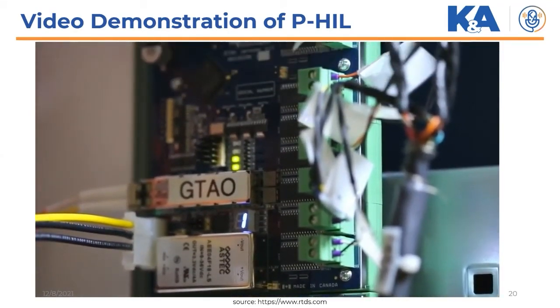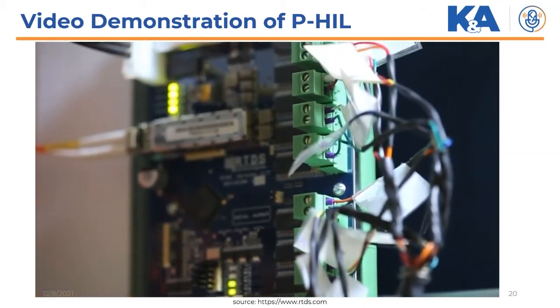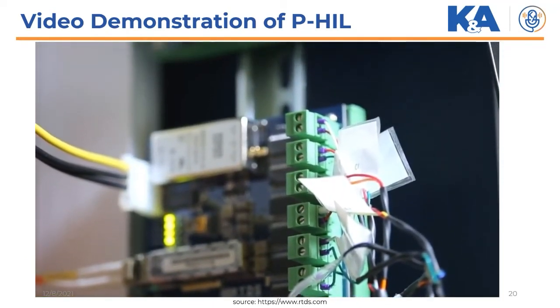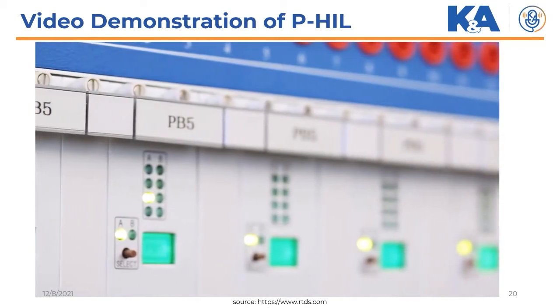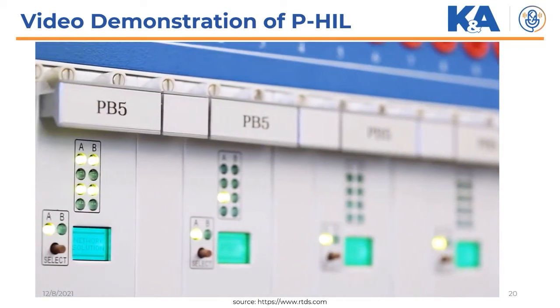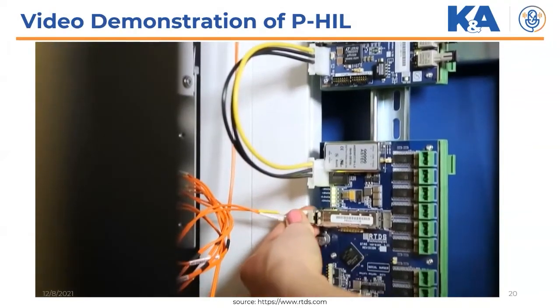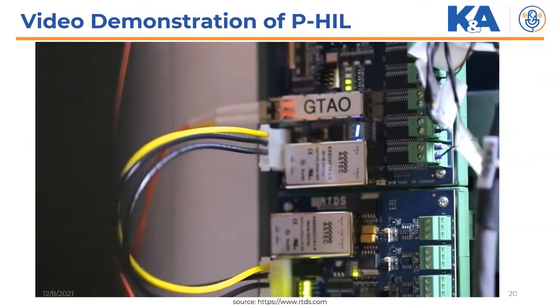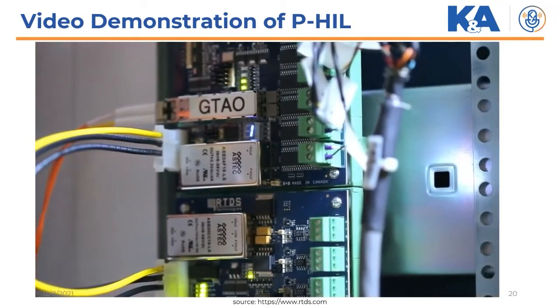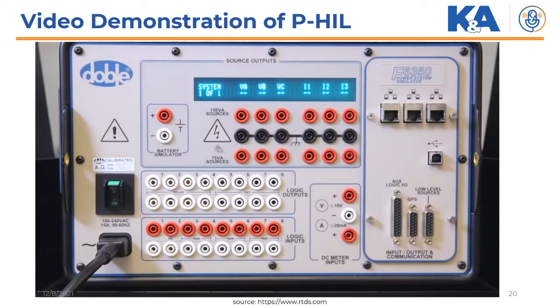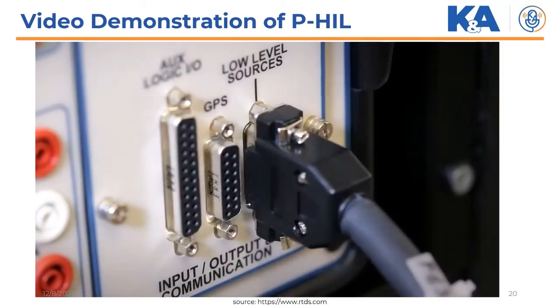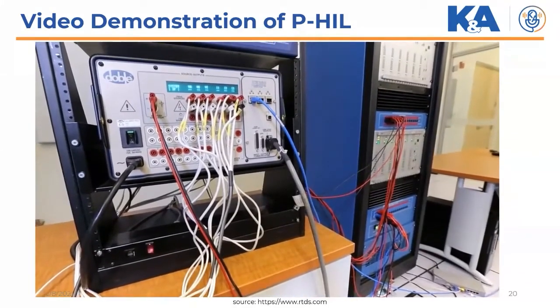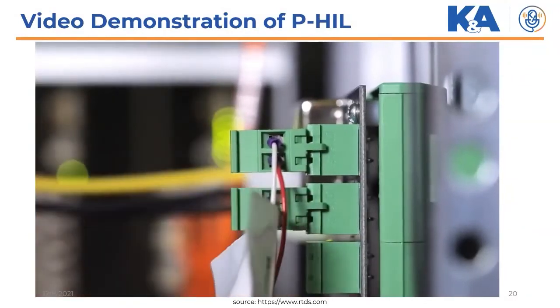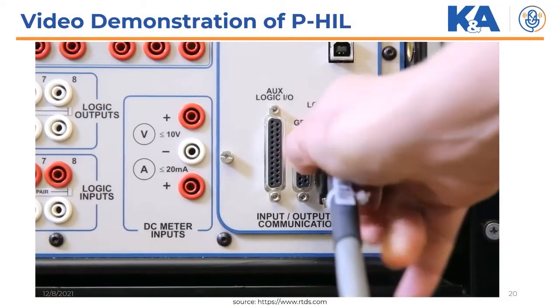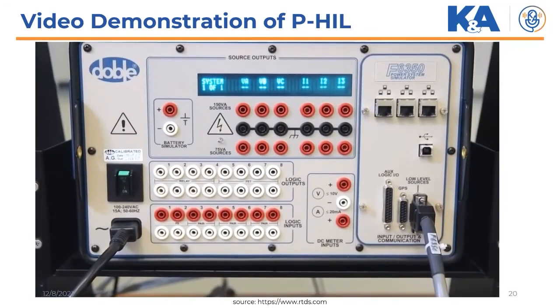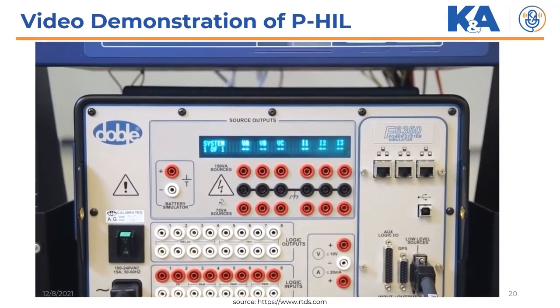The GTAO card features 12 optically isolated, 16-bit digital to analog conversion channels. The signals are sent from a PB5 processor card participating in the simulation to the GTAO card via fiber optic cable. The GTAO card has a maximum output range of plus or minus 10 volts peak. A power amplifier is used to scale up the output waveform and test the relay using its in-service operating voltages and currents. The GTAO outputs are connected to the amplifier's input channels, and gain levels are carefully set and tested to ensure that the amplifier's output values are as expected.